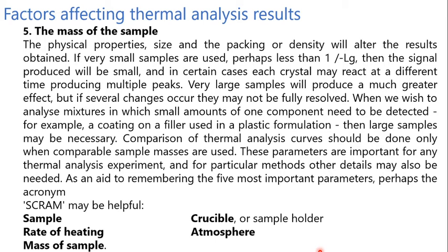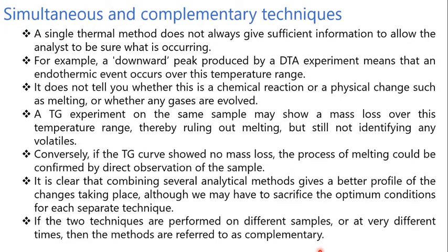These parameters are important for any thermal analysis experiment and for particular methods. Other details may also be needed. As an aid to remembering the five most important parameters, perhaps the acronym we have used here, SCRAM, that is sample, crucible or sample holder, rate of heating, atmosphere and mass of the sample.